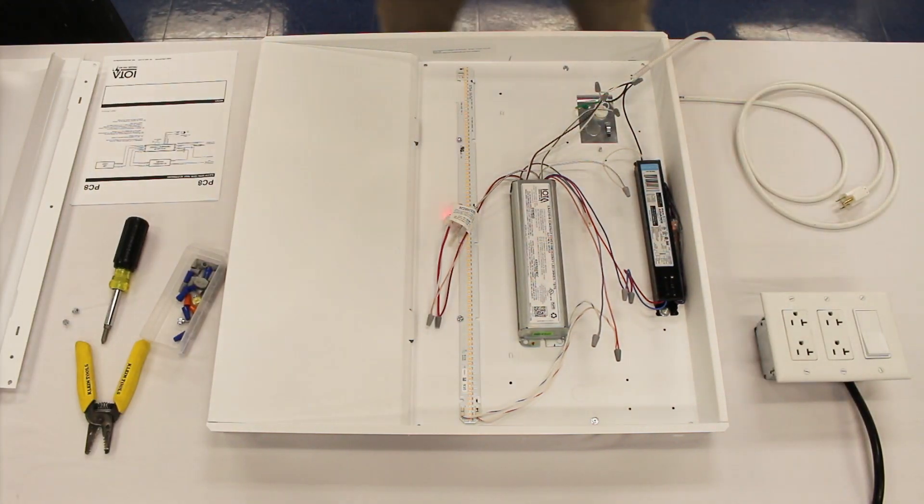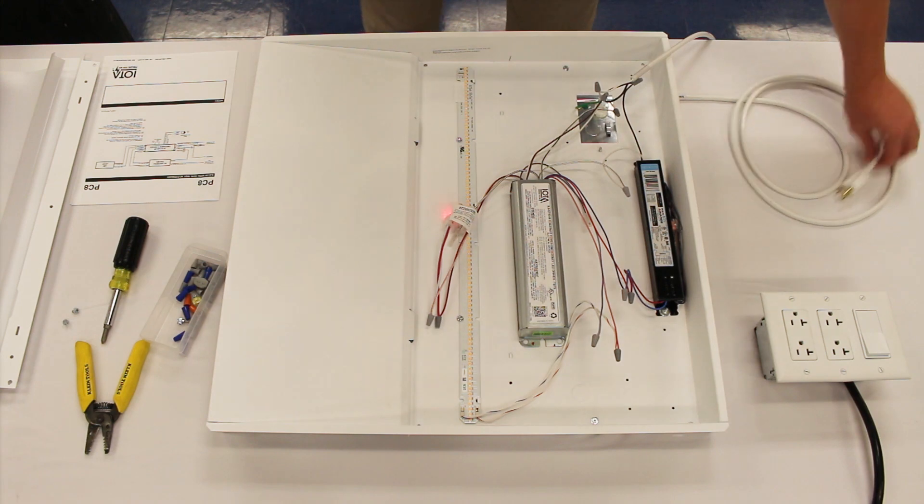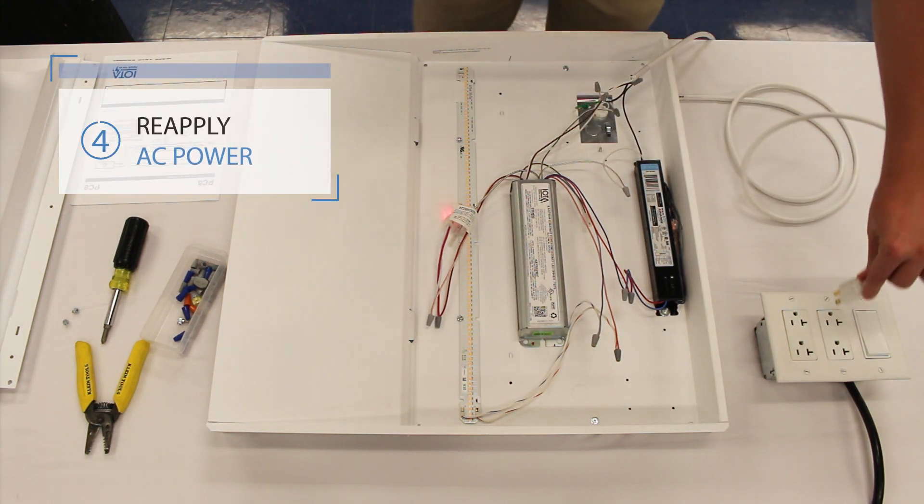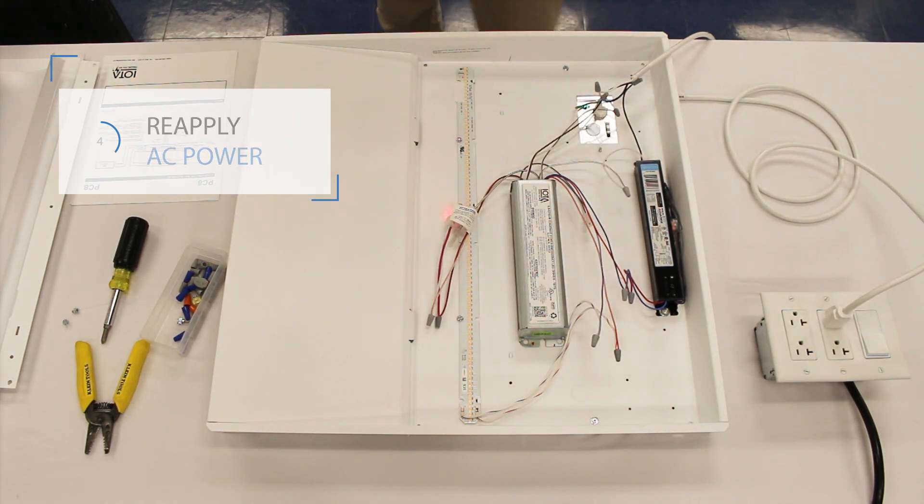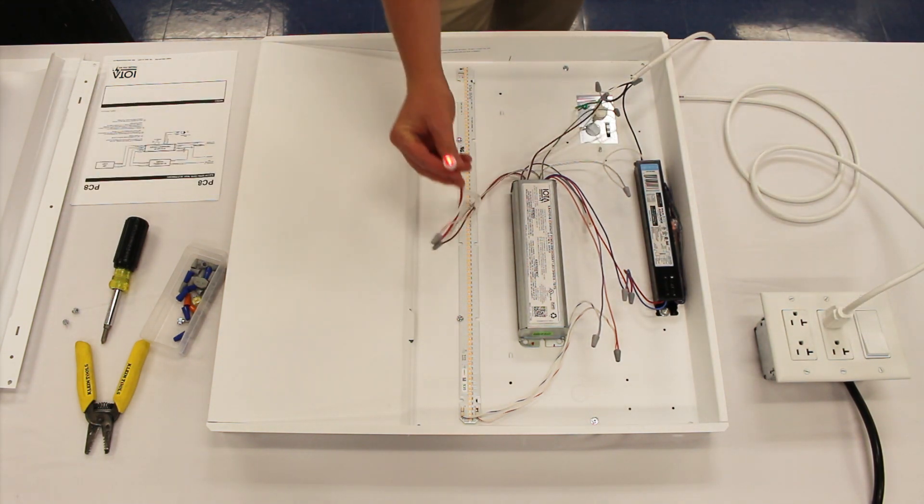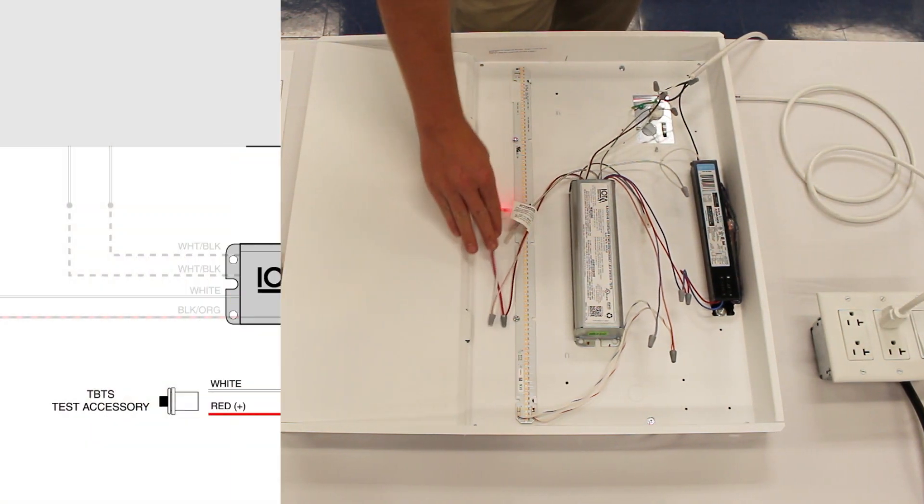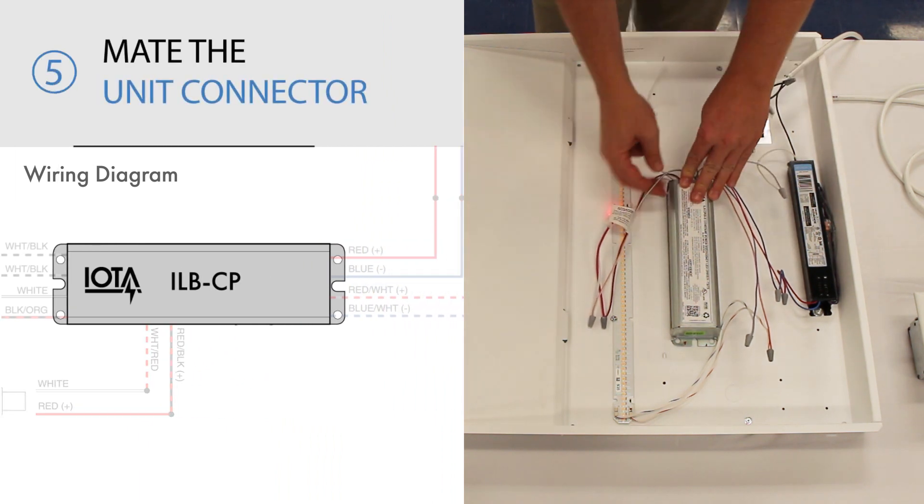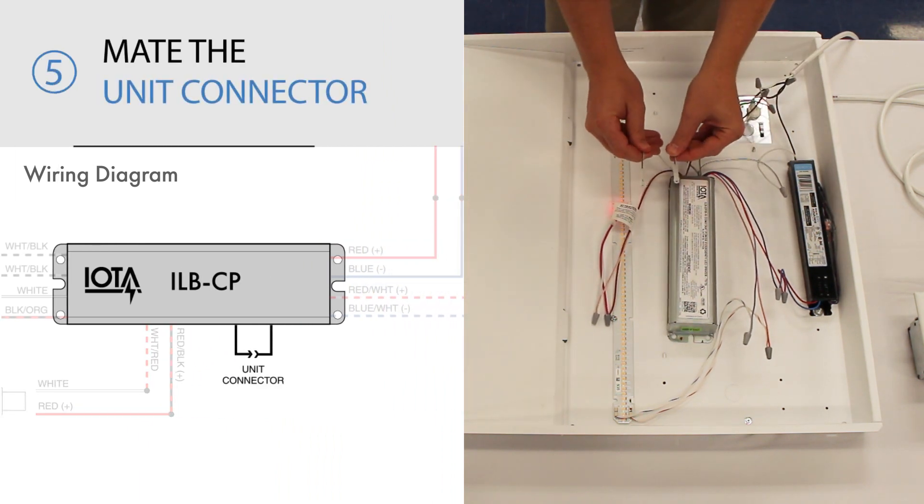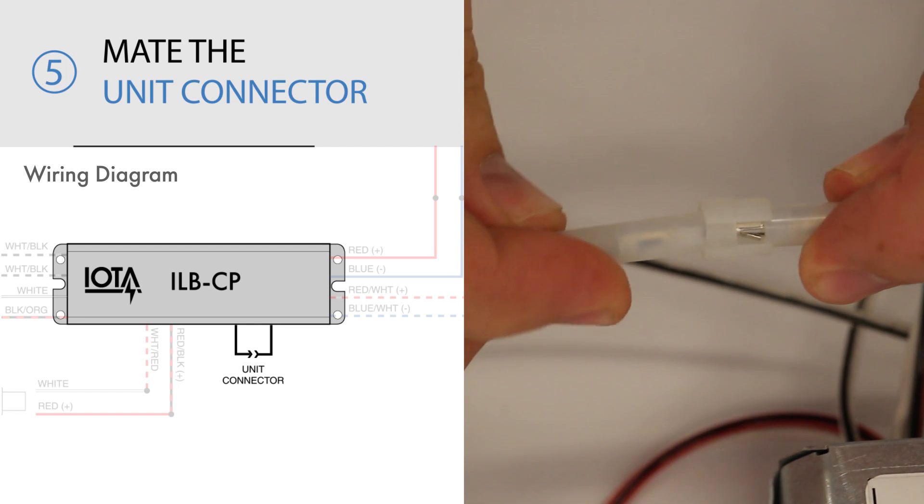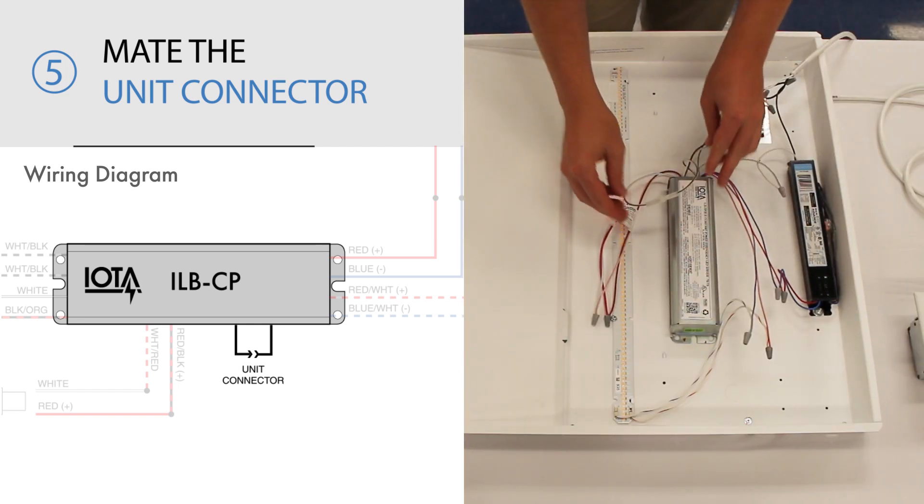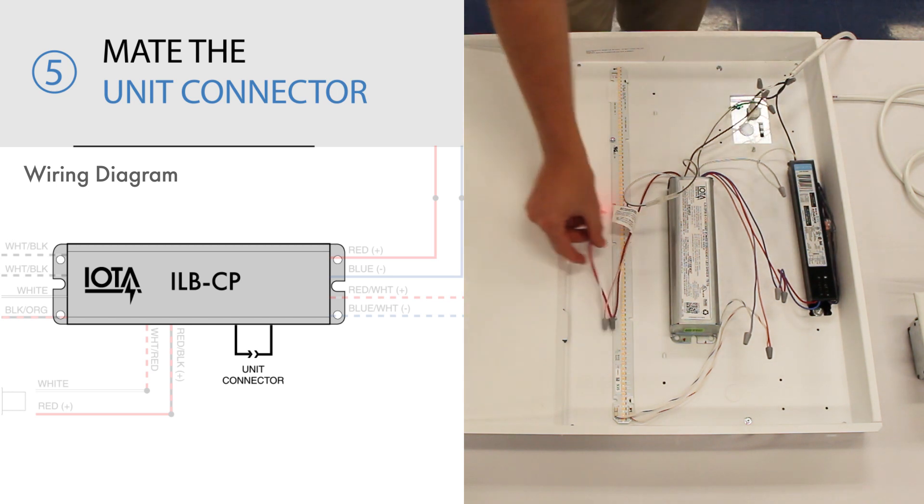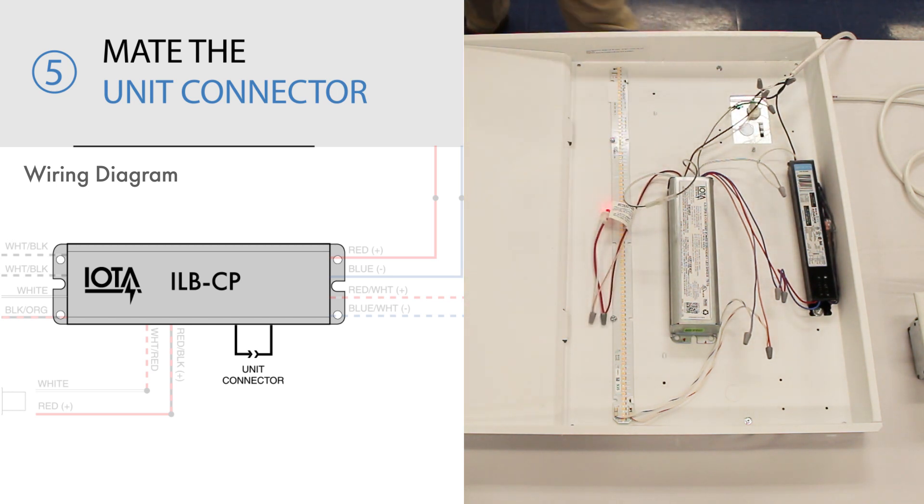The wiring of your ILB-CP unit is now almost complete, and at this point you may reapply AC power to your fixture. Once AC power has been reapplied, the very last step is to mate the ILB-CP's unit connector. Note, be sure to not mate the unit connector until permanent AC power has been applied to your fixture, or you will begin to drain the ILB-CP's internal batteries and may hinder its proper emergency operation.